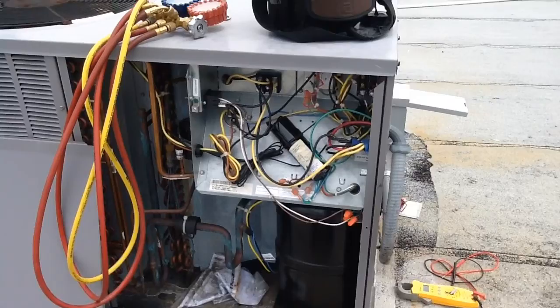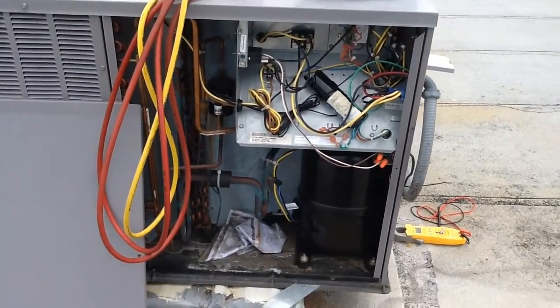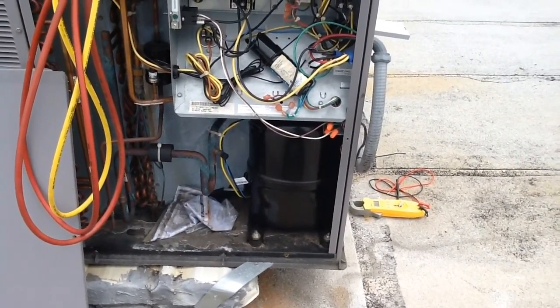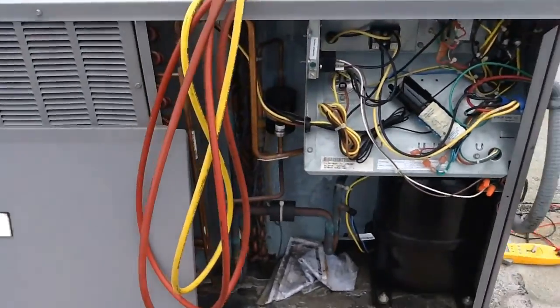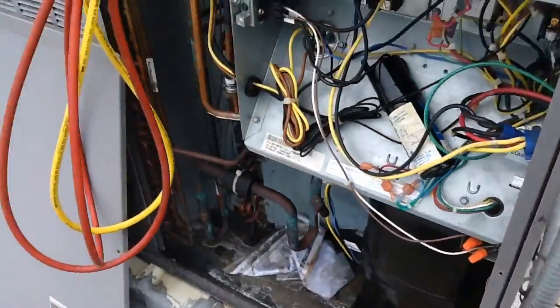When I just came up here I checked for high voltage — didn't have high voltage, so the breaker was tripped. We're going to test this reciprocating motor first before I turn it on, because I hate to walk back up and down and make sure this thing is working.